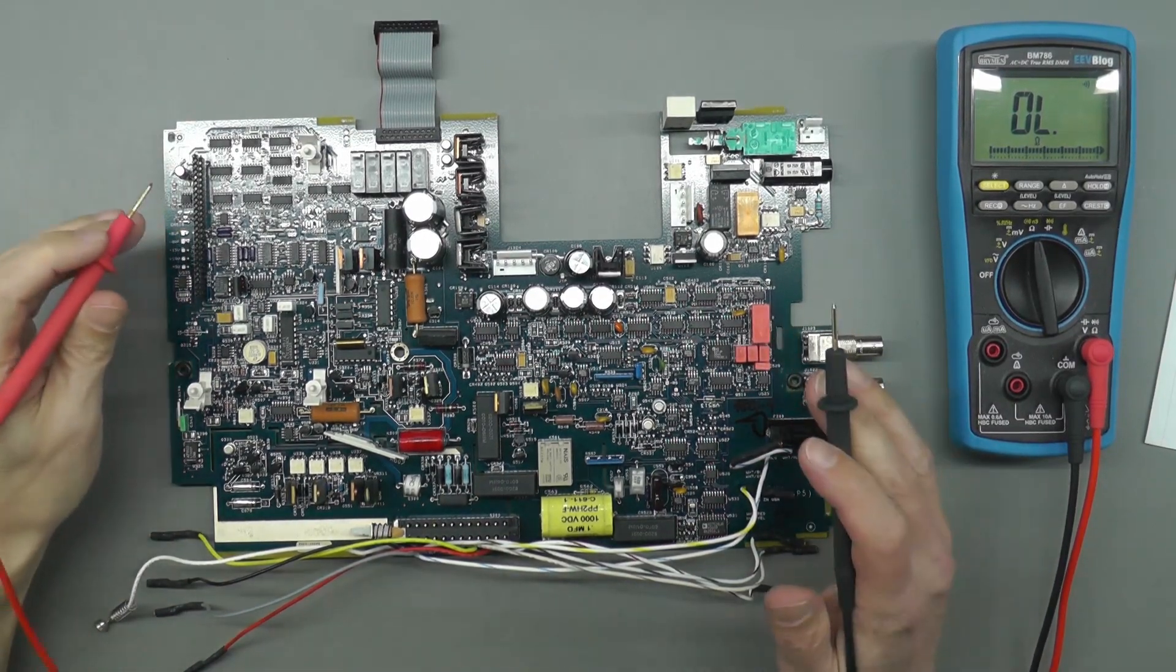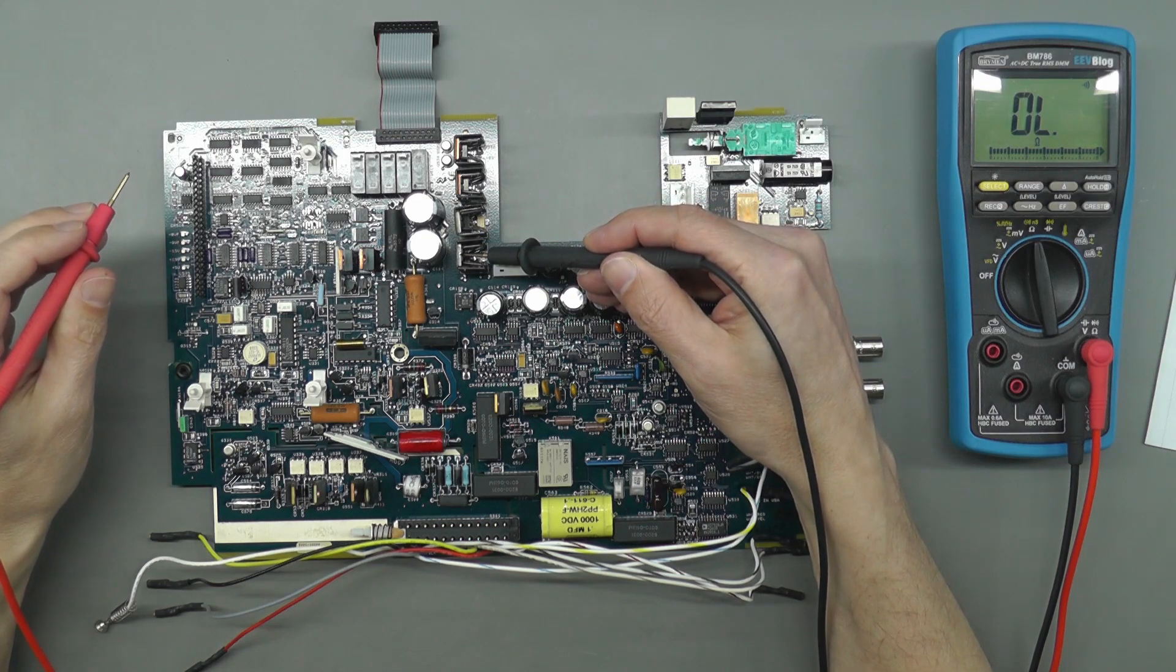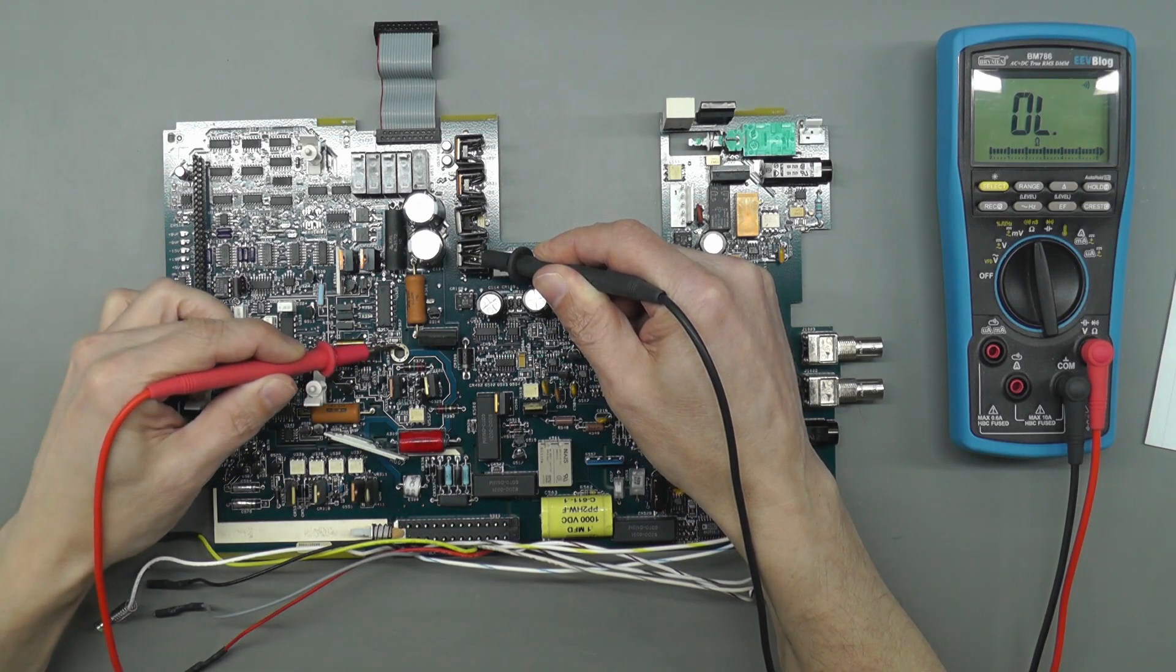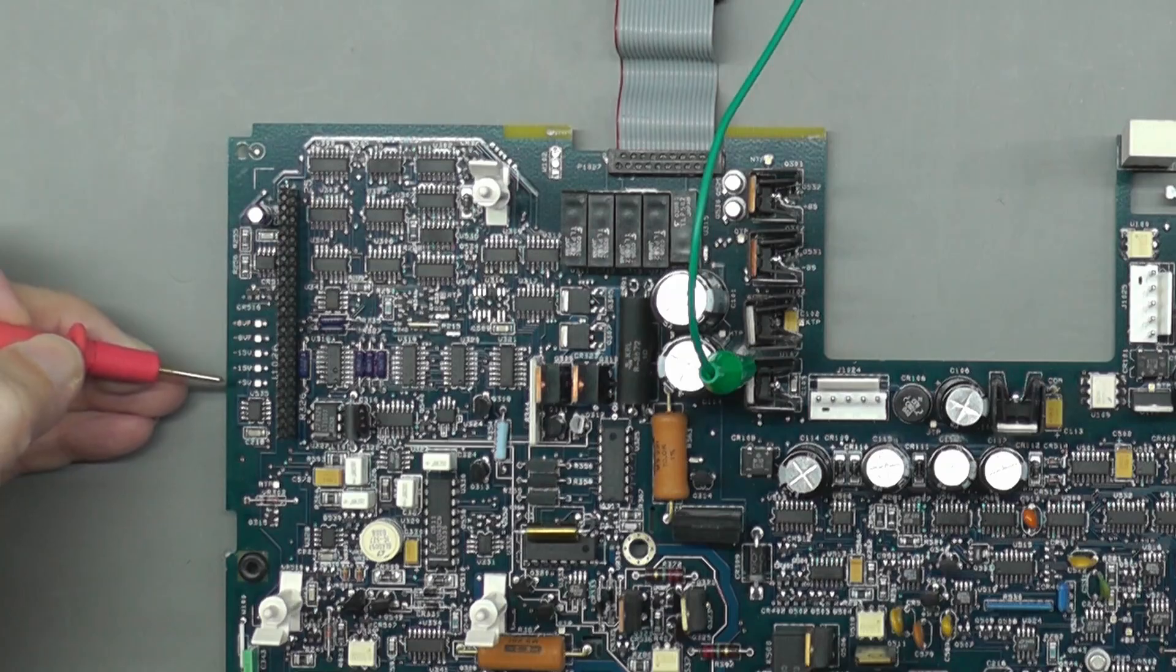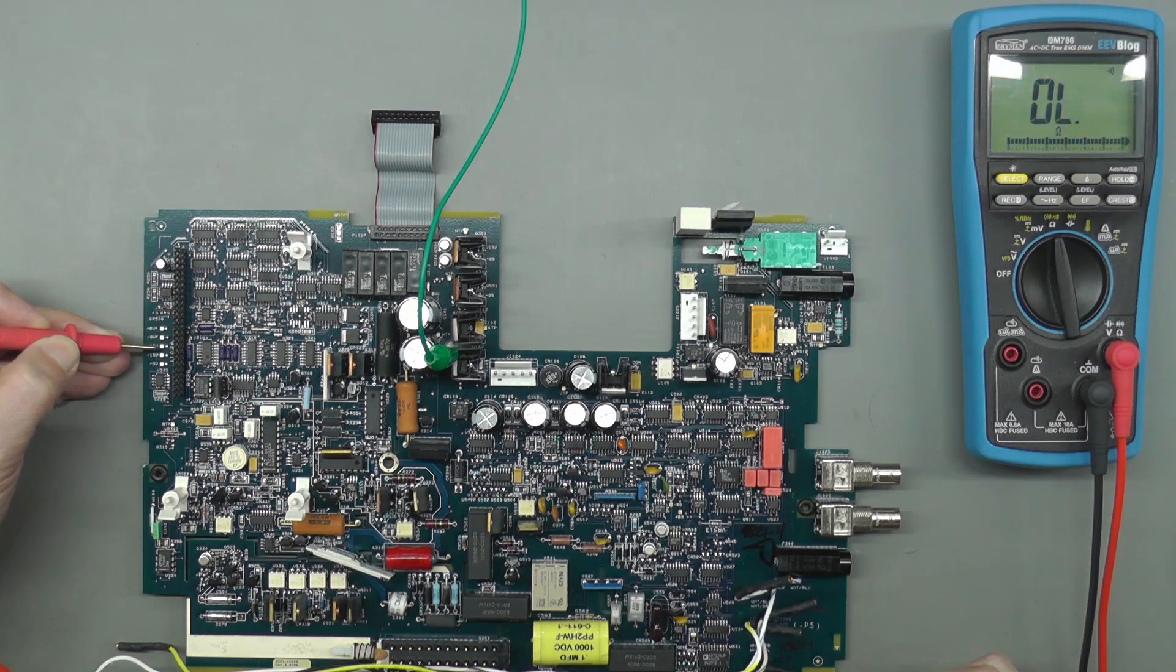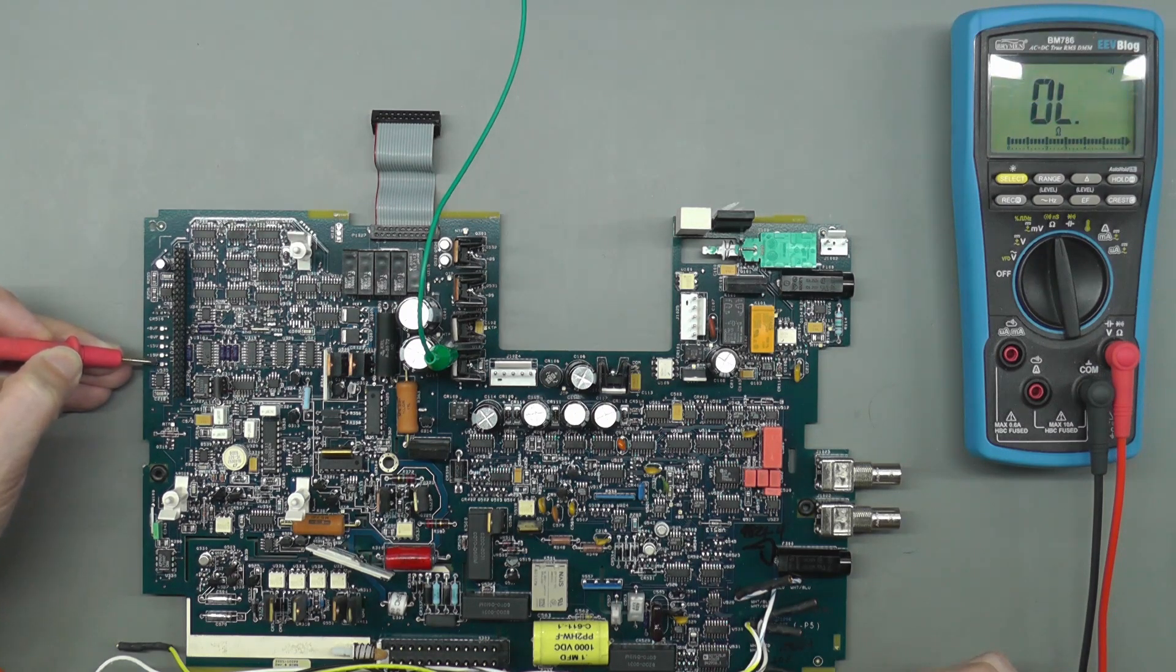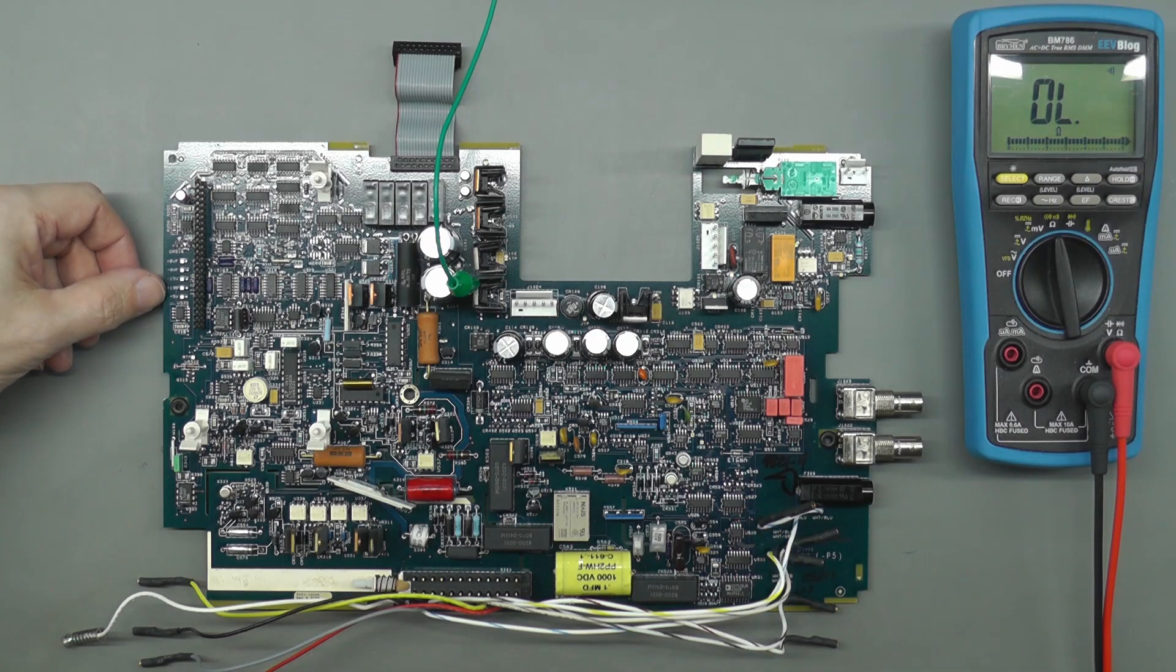Okay, so let's start probing the board. First thing I'm going to need is a good zero volts. These are the plus and minus 15 volt regulators, this one being the positive 15 volt, the 7815. The tab is zero volts. At the left hand side of the board there are some test points here: plus and minus VF, minus 15, positive 15, and plus 5. Let me go down them looking for shorts. The minus 15 one is showing about 20 ohms, the positive 15 about the same, and about 25 ohms for the plus 5 volt.